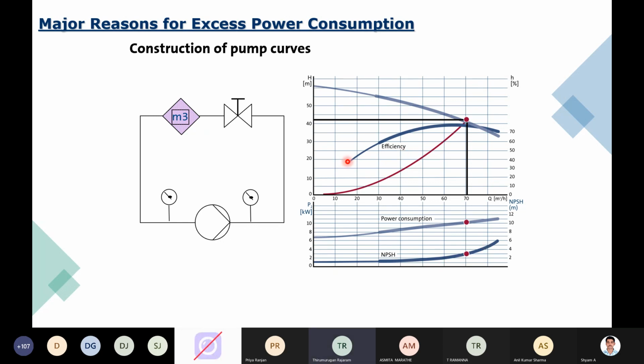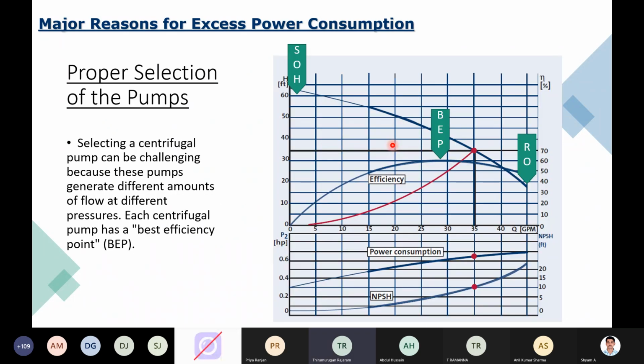Okay, and if you see the efficiency curve, it will rise to the top, and this particular point we call the best efficiency point. After that, it becomes flat, or it will be drooping to the end of the curve. So this is your basic characteristic, and whenever you want to buy a product, we insist on having it very close to the best efficiency point. If you select a pump here, obviously the efficiency is good, and your energy consumption will be slightly lower. But if you select a pump somewhere here, you can see there is a drop in efficiency, and that impacts your energy consumption also. So understanding the curve of all the products helps you understand its performance and arrive at what is really required in this case. Okay, so I have briefed you about the performance curve.